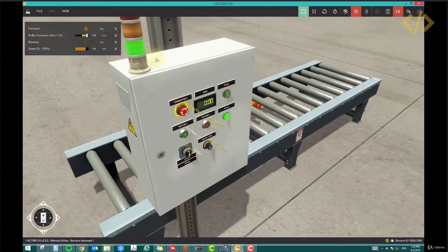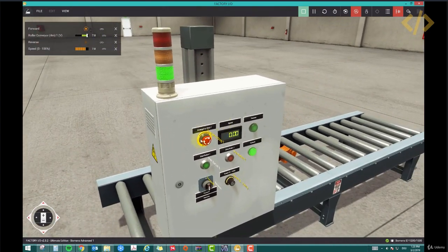Great. Now we need to check our e-stop. So I will stop it and I press e-stop. In this case, you can see it's blinking. From a far distance, it can be easily monitored. And if I release it, it will be stopped because e-stop is released. Again, it's blinking, and then it's stopped, and I can start the motor.